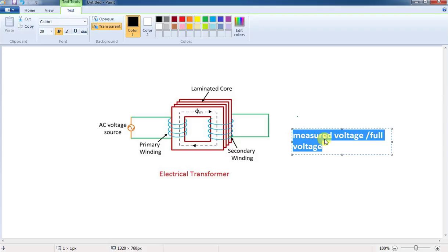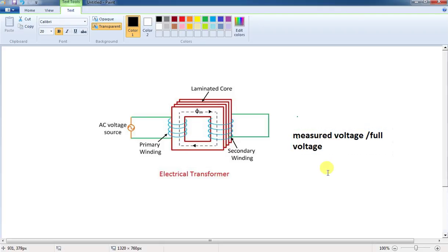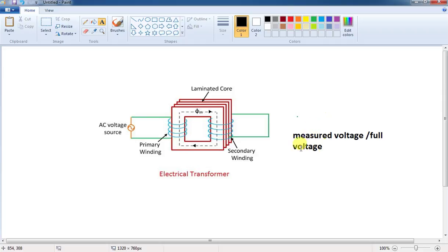If you take typical percentage impedance values, they are in the range of 5, 6, 7, 8, or 10. In that range, you will rate the transformer. So, the percentage impedance is the result of this measurement.